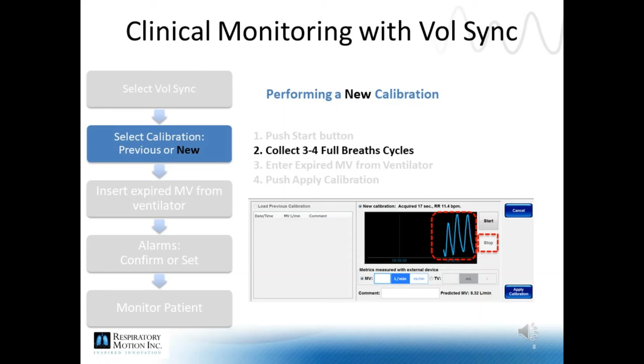To perform the calibration, the system will need to collect at least 3 to 4 full breath cycles. For best results, this should be performed when the patient is under full mechanical ventilation. If the patient is breathing spontaneously, you should try to collect the breaths during a reasonably quiet period without erratic patient activity or manipulation by staff. Once you have collected the 3 to 4 breaths, touch Stop.